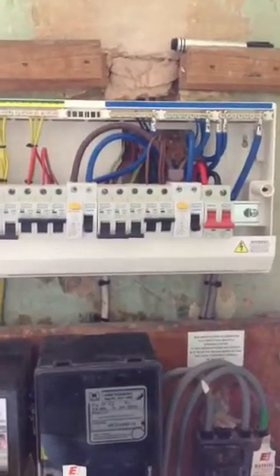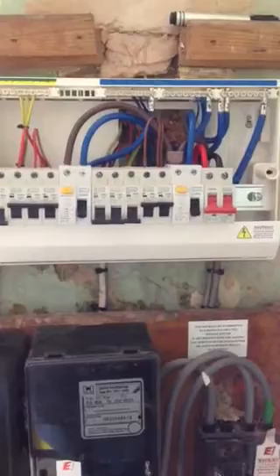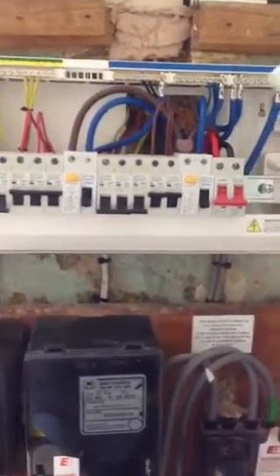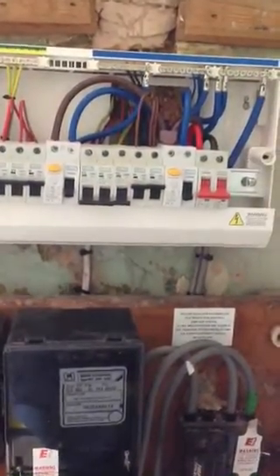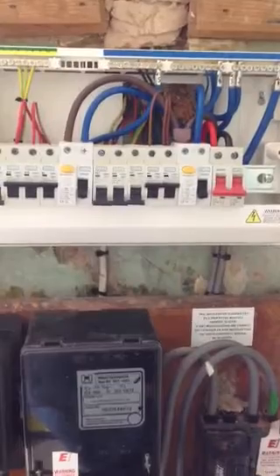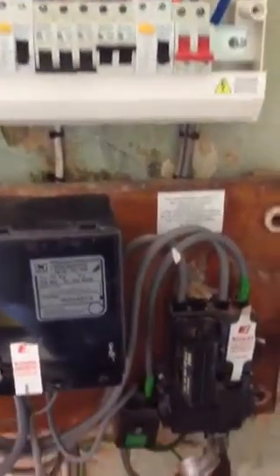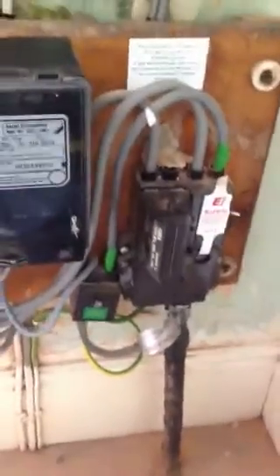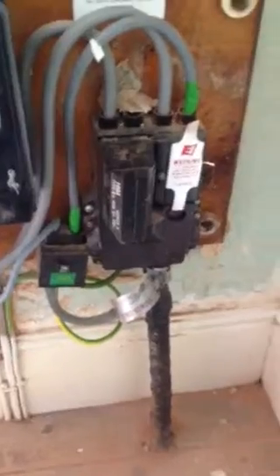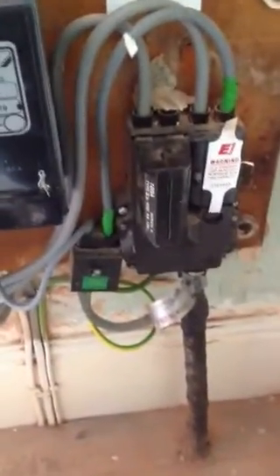We've replaced the consumer unit now, and one of the first tests we're required to do before we switch on the main switch is to carry out an earth fault loop impedance test to ascertain the good connection to earth. This system here is a protective multiple earth, or TN-C-S.